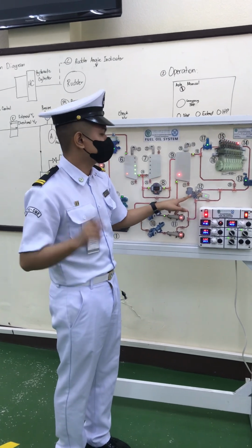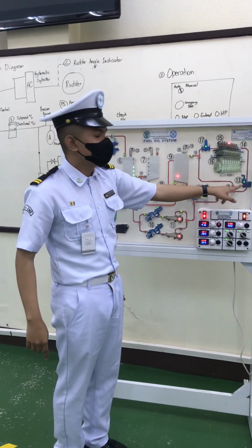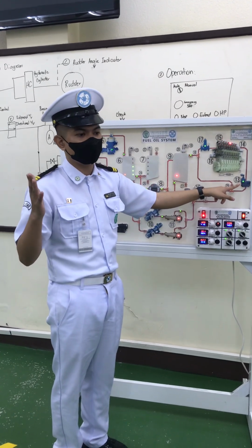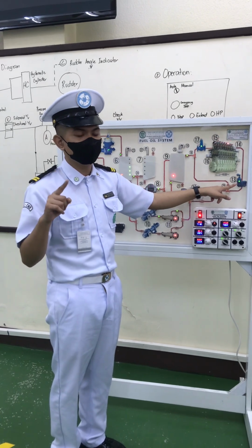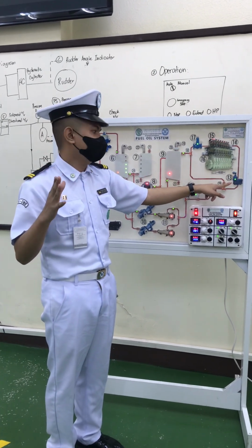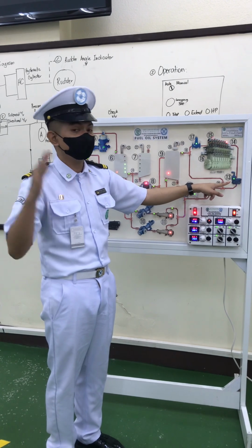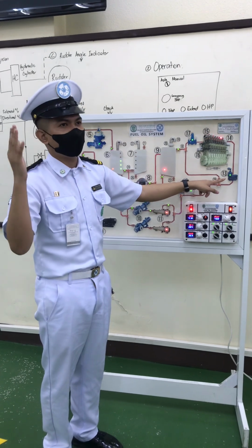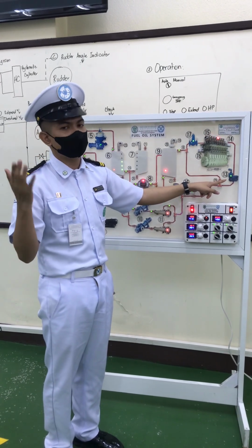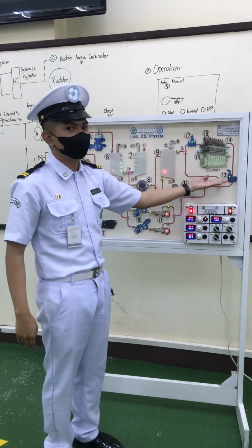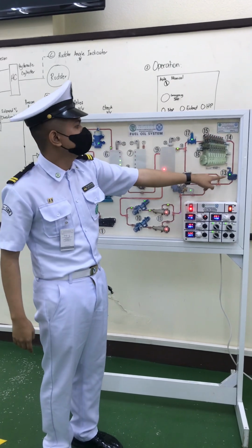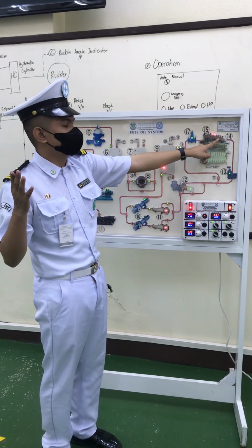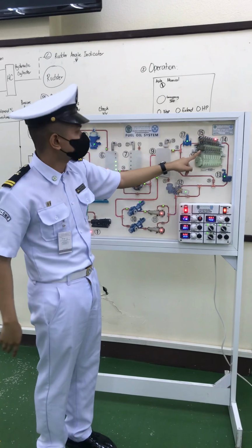that is regulated by the viscosity regulator will now go to the heated filter. The heated filter acts so that in case there are solidified substances in the fuel, they will be dissolved, and the fuel oil will be heated again to increase the temperature and have the correct viscosity. And again, if there are still contaminants, they will be filtered by the heated filter. Once done, it will go to the fuel injector, where it will be injected into the engine for the operation.